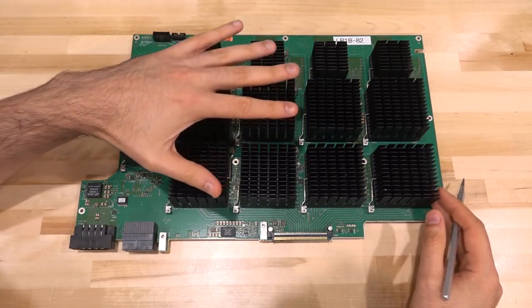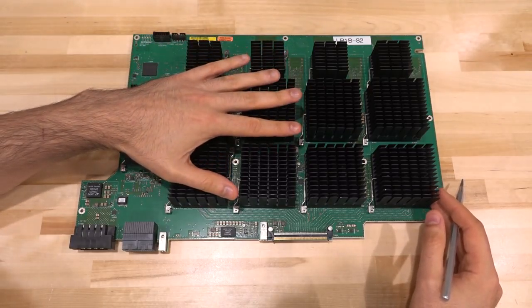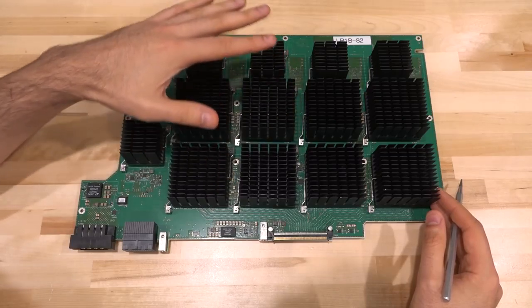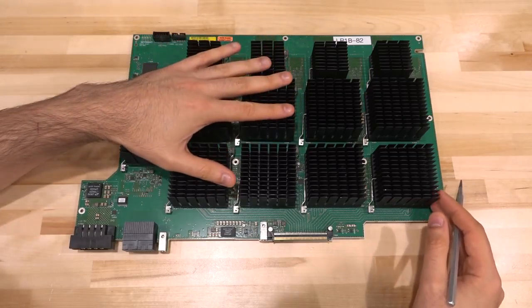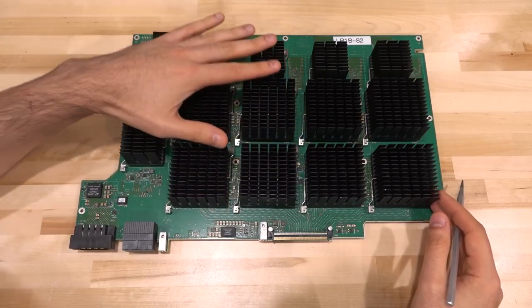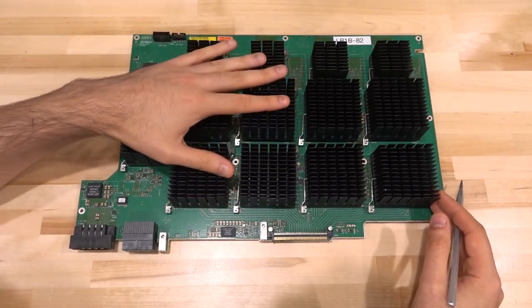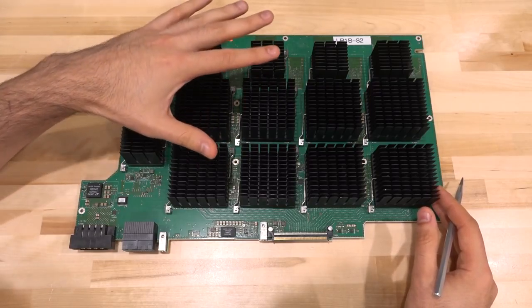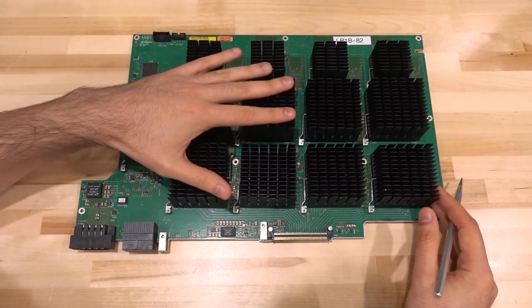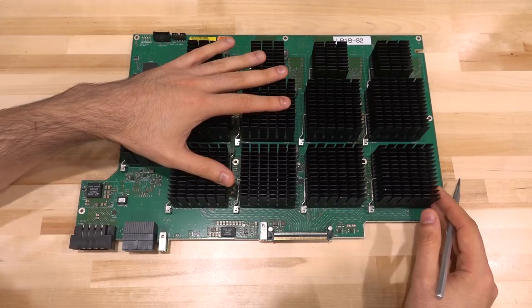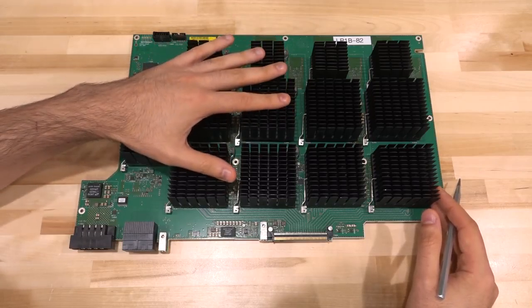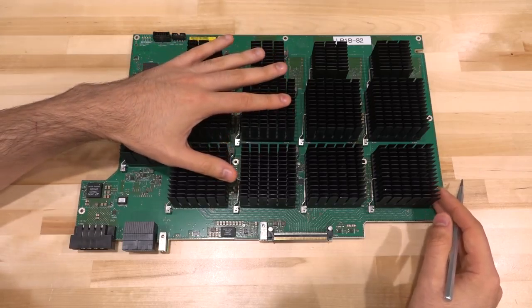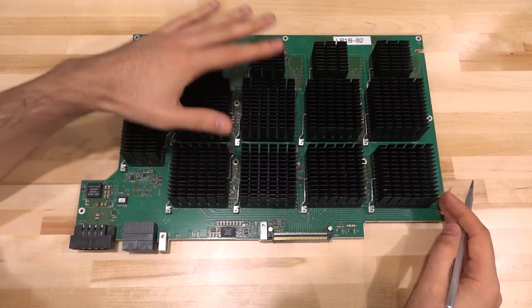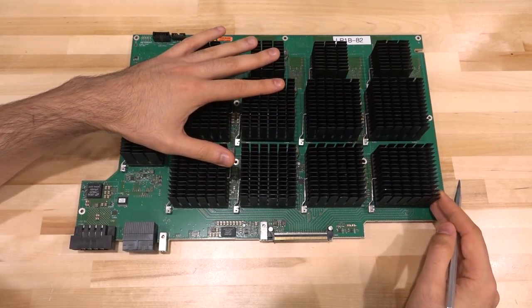Now keep in mind there are 4 of these inside a 4-channel oscilloscope. That's because that's how you're going to get 256 gigasample per second, 110 gigahertz per channel, regardless of how the channels are configured. So it doesn't matter if you have 1 channel on or if you have 4 channels on, you have one of these dedicated per channel. And that's one of the reasons why it's $1.3 million, because you have so much independent redundant hardware to get the performance per channel totally unaffected by how much data you're collecting.